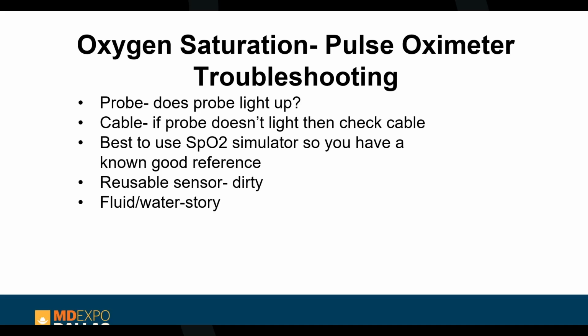No one ever admitted to getting the cable wet or dunking it under water. So I started asking questions of the unit: when do you have these plugged in when you take the patient in there, and does it ever get wet? And they said, oh yeah, we just take it back out of the water, and we've been having a lot of problems with our pulse oximeter cables. I'm like, look, that's it. The cable that I had at my desk sat there long enough that by the time the Philips guy got there to look at it, when I thought I was so smart, it had dried out and worked fine.